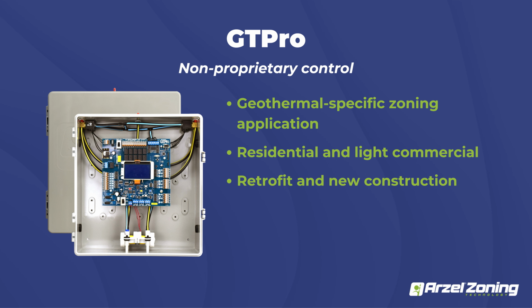Besides just that outdoor air temperature sensor and the leaving air sensor, it's also going to ship with a loop temperature sensor, which will go on your return loop of your geo, and it's going to help with the staging as well. So you're able to pick not only just time and temperature, but also that loop temperature. It's called a loop reset. So as your temperature starts either declining or increasing on your loop, the panel will start staging your equipment more aggressively to make up for that loss in temperature from the water. So it's a really nice panel when you guys are doing geothermal equipment.